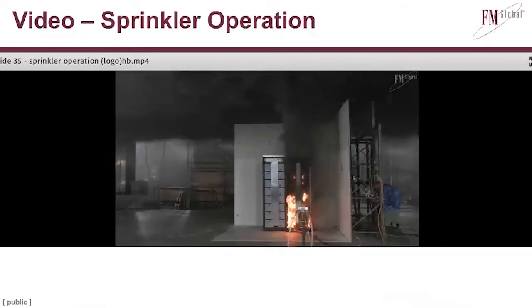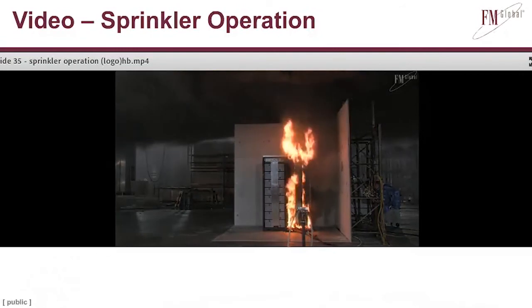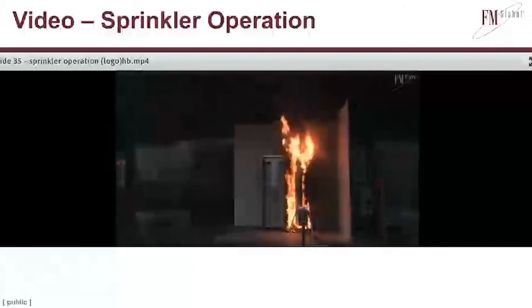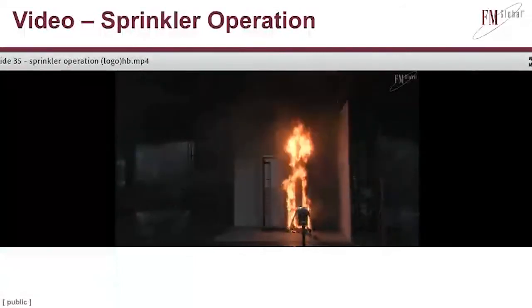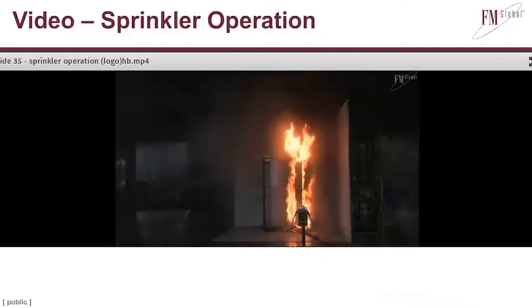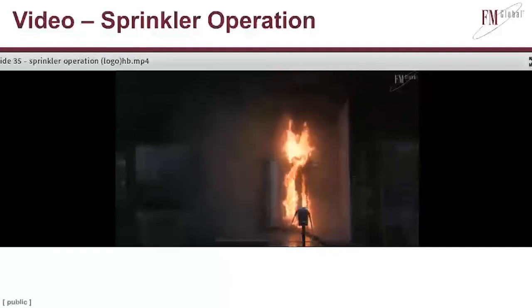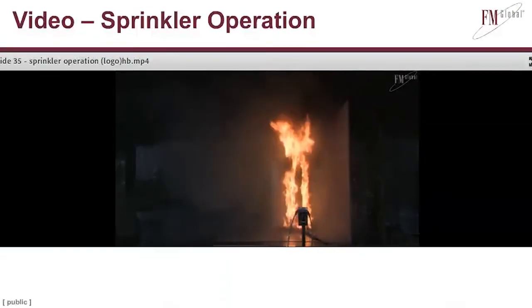These modules weigh about 160 pounds each. There are 16 of them, so this represents a very large thermal mass. The spread of heat through this rack can be somewhat slow because you have to heat all that mass up. But you can see the increased smoke production. And as this develops, now you can see a large jump in the fire. I think what happens there is that you've heated up a lot of batteries, and now you have a mass thermal runaway event of a lot of batteries, and then you see a large increase in fire size, and that's that first sprinkler operation. So all the additional heat just got pushed up to the ceiling.